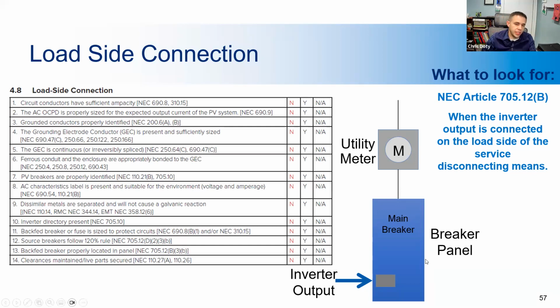So this is basically to ensure that nowhere in the panel will there be more current than the bus bar can handle. So if you have a 100 amp service and a 20 amp backfeed breaker, you have 100 amps coming in the top of the panel and 20 amps coming in the bottom, which would only happen if you are pulling 120 amps for something, which is a lot of amps. At no point in that panel should there be 120 amps in a single place, which could damage the bus bar or melt it.